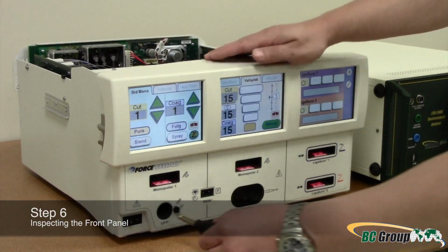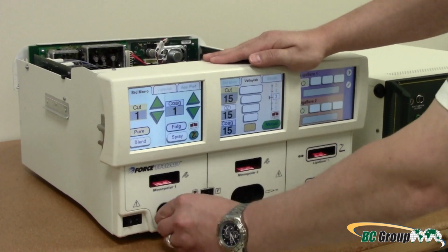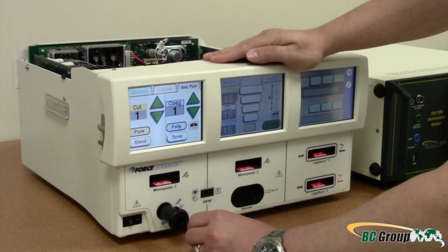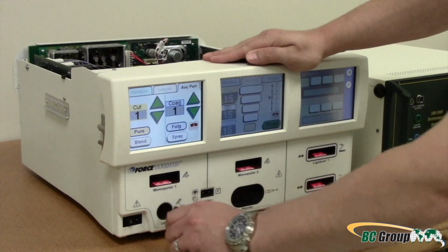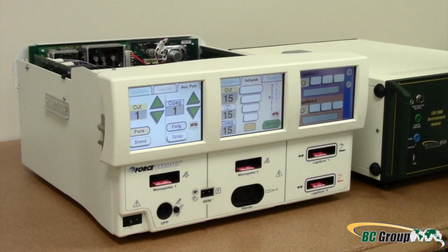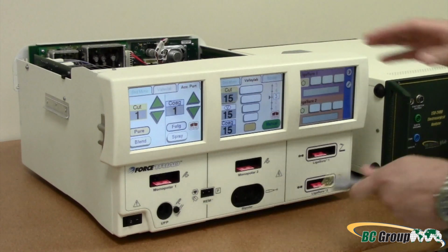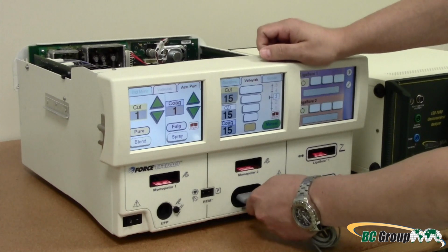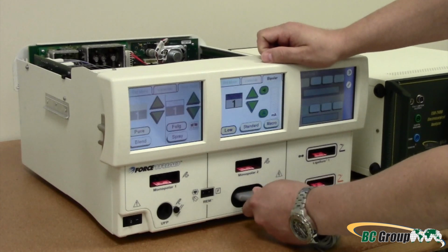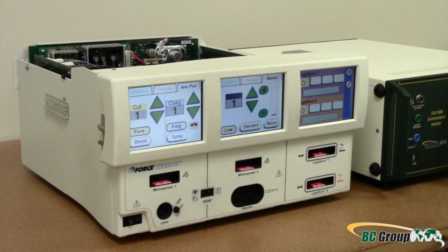Check the UFP port for obstructions or damage. Check for a secure fit by inserting the UFP adapter into the receptacle. Verify that the UFP tab becomes active. Check the bipolar port for obstructions or damage. Insert the bipolar cable into the port to verify a secure fit. Verify that the bipolar tab becomes active.